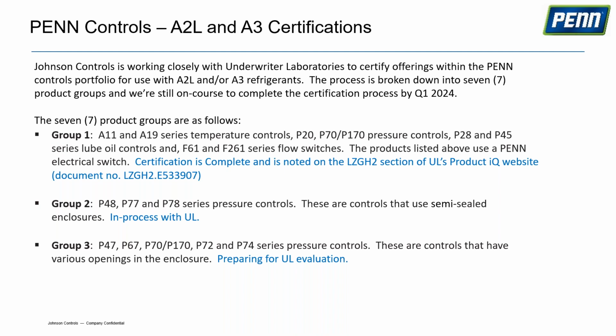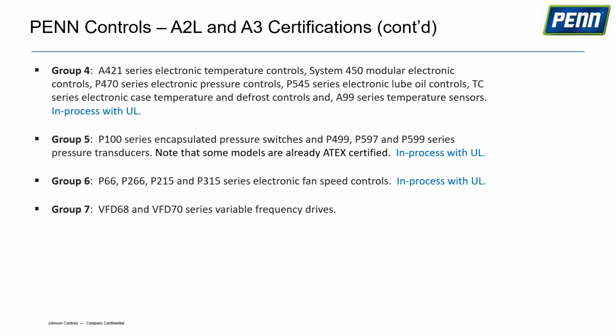Our Group 3, again more pressure controls, we're preparing for UL evaluation. Group 4 are mainly our electronic controls, also in process with UL. In a lot of cases we may have to switch to what we call sealed relays and non-vented type relays, to make sure there can't be any source of ignition with refrigerant making its way into the relay chamber.